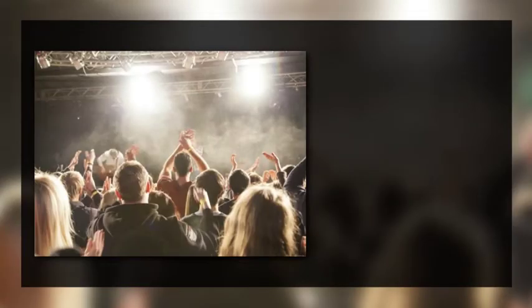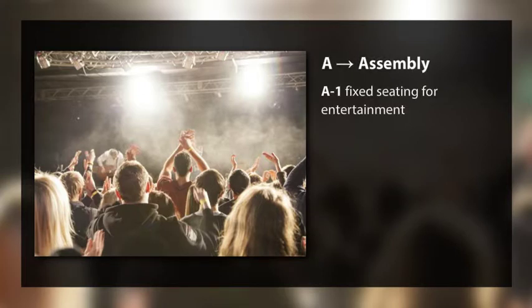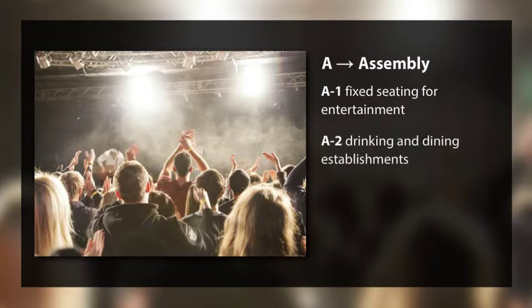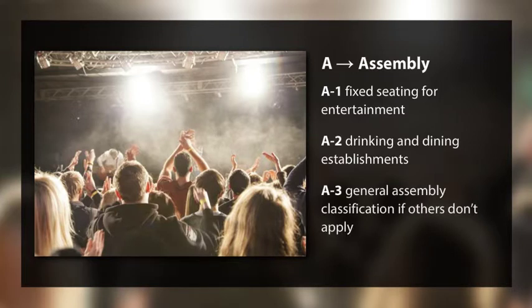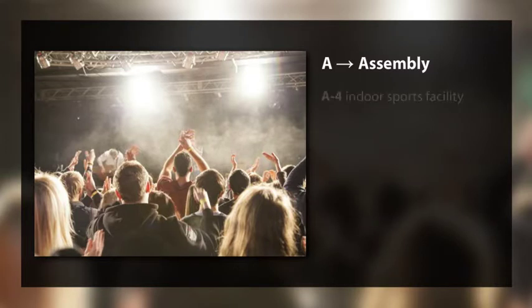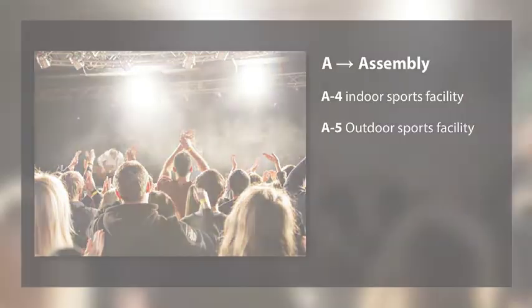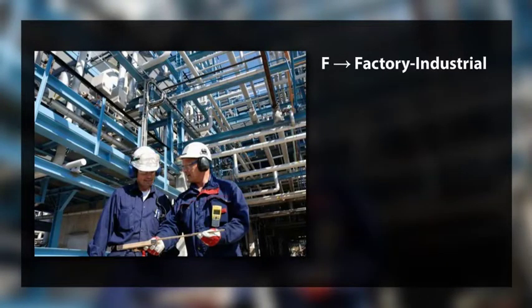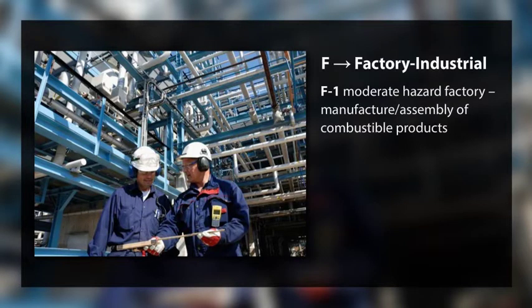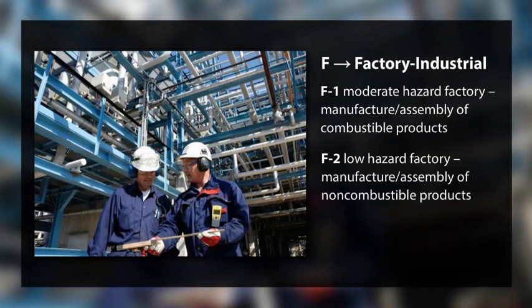The occupancy subgroups for specific classifications are as follows. Assembly subgroups: A-1 — fixed seating for entertainment, such as a theater or concert hall; A-2 — drinking and dining establishments; A-3 — general assembly classification if others don't apply; A-4 — indoor sports facility; A-5 — outdoor sports facility. Factory Industrial subgroups: F-1 — moderate hazard factory, manufacture or assembly of combustible products; F-2 — low hazard factory, manufacture or assembly of non-combustible products.